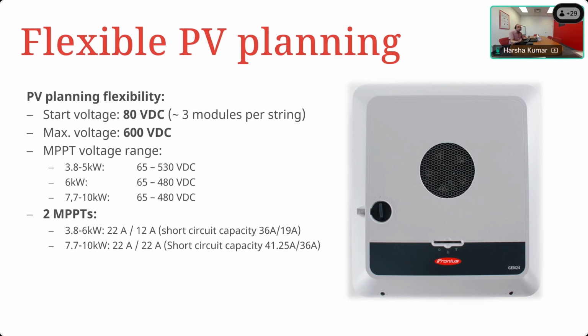It is 50-50 on the bigger power classes. So the usable current on both MPPTs for the bigger power classes is 22 amperes each, and the short circuit current capacity for MPP Tracker 1 is 41.25 amperes, and for MPP Tracker 2 is 36 amperes. So this again will enable you to use the higher power PV modules, including the bifacials, which are now currently on the market. Okay. In addition to that, we have one battery input for 22 amperes, and that should also give you an idea that these are only able to work with high voltage batteries. Okay, so that is the reason that the current there is that low.